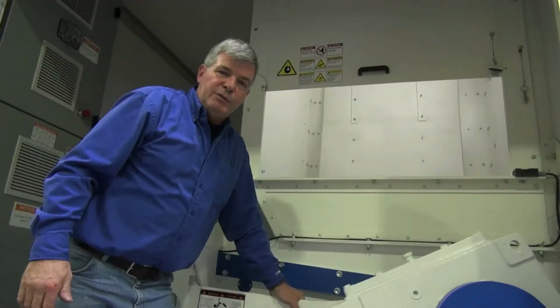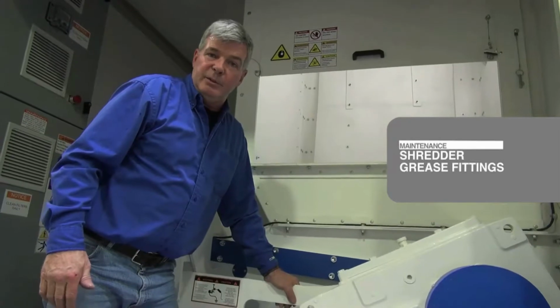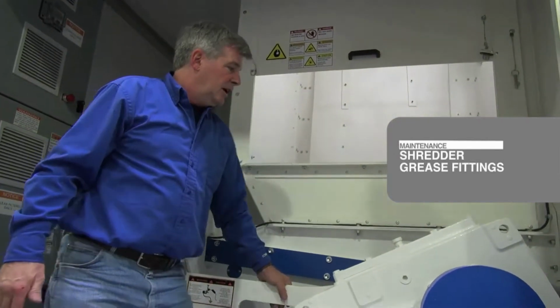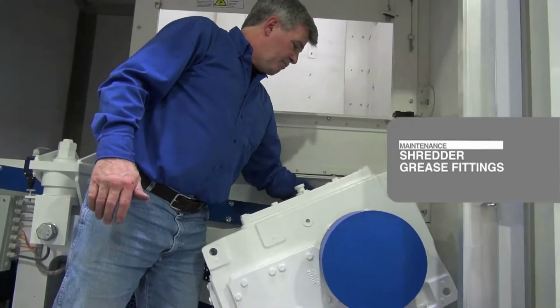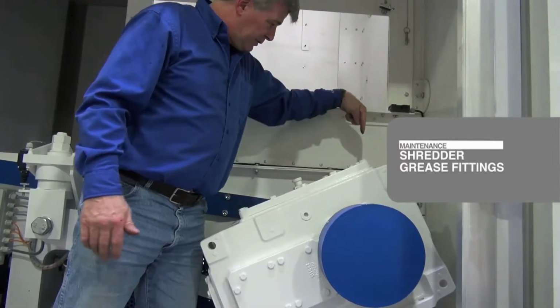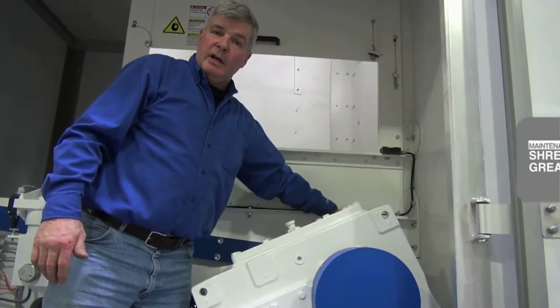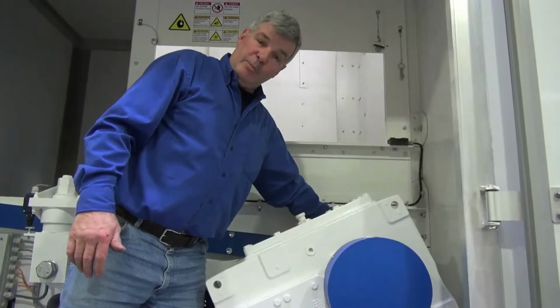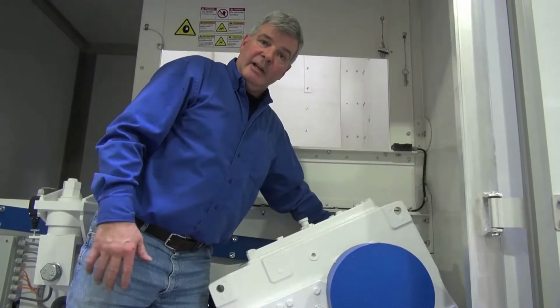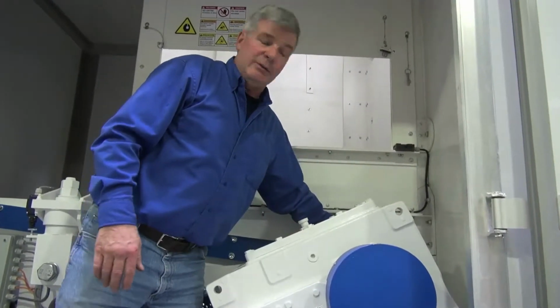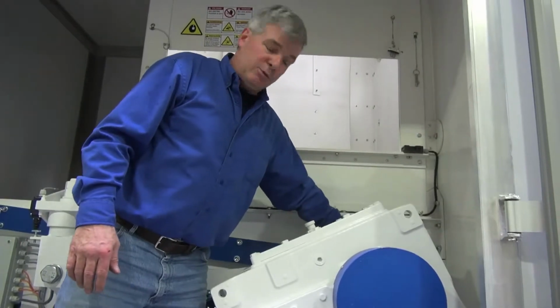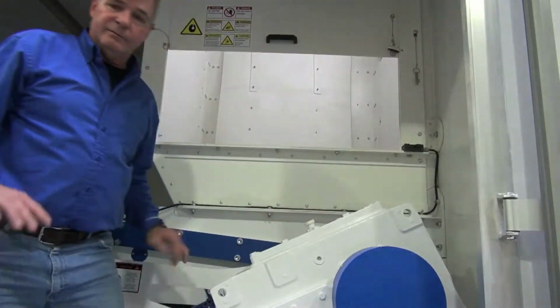There are several grease fittings on the machine that need to be taken care of. The first one is on the bearing behind the gearbox. There is a grease fitting right there. The greasing amounts and how often you have to do them are in the manual. It's every 50 hours, 3 pumps is what we say. The manual will tell you how many ounces, but every 50 hours, 3 pumps of grease in your rotor bearing.